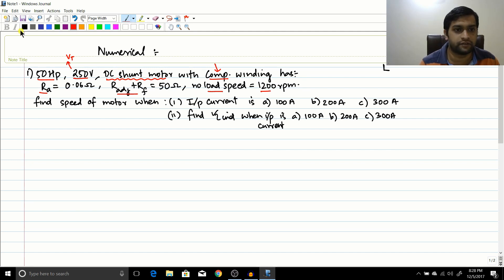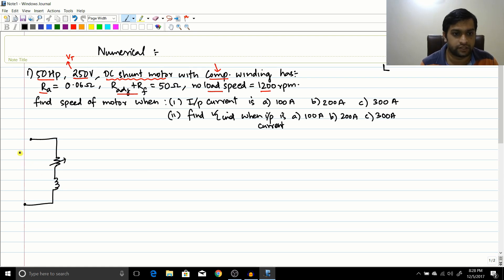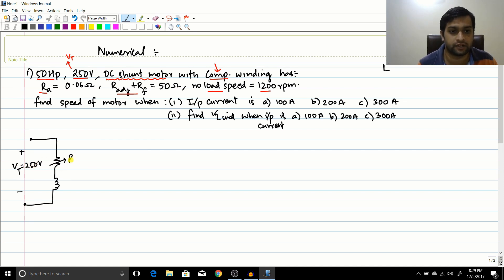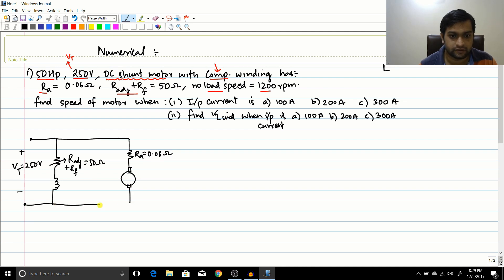Let us draw the equivalent circuit so we can put down what we have. It is a shunt motor, so there is a shunt winding. The equivalent circuit shows Vt = 250 volts, R_adjust plus R_field equals 50 ohms, and in the armature branch, Ra = 0.06 ohms. The armature generates a voltage Ea.